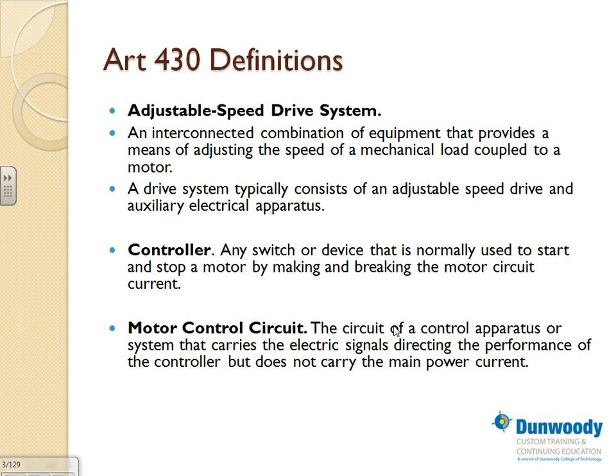The other type of controller, as we saw, is across the line. We call them NEMAs, NEMA 1 through NEMA 9, and you can find them online. That's what I like about the DeWalt: you can find all the NEMA sizes and which NEMA fits what horsepower at what voltage, single phase or three phase. Really cool, from NEMA 00 all the way to NEMA 9. The problem with NEMAs, as we all know, is they're across the line, with no voltage reduction. The inrush on the motor is so huge if your motor is high in horsepower that it could dim or dip the voltage, number one, and cause nuisance tripping for certain things in your building.